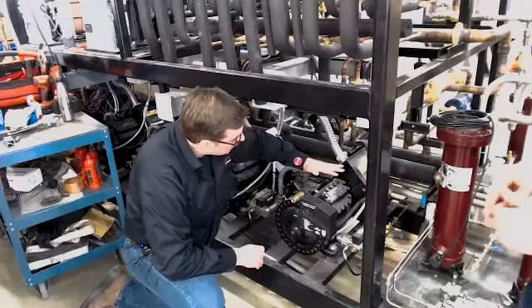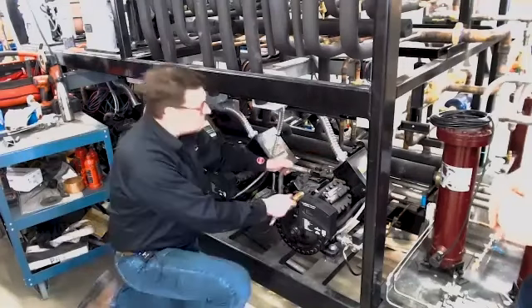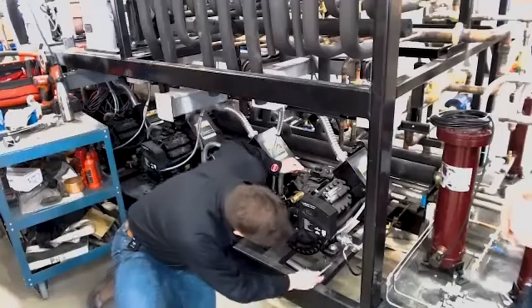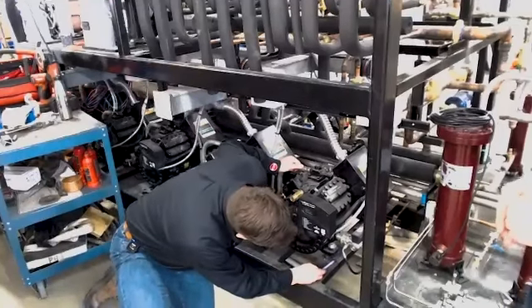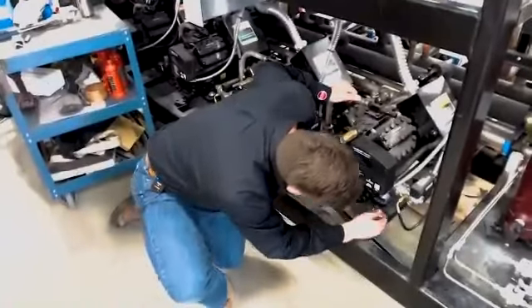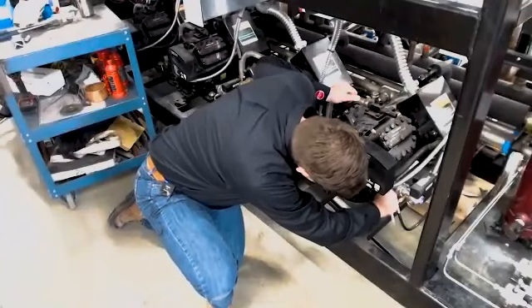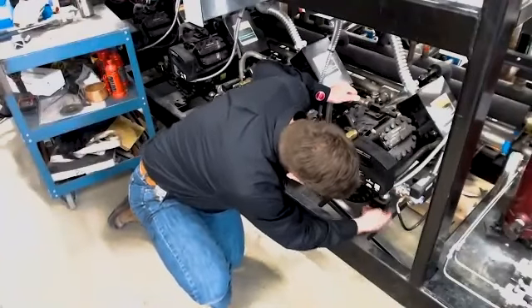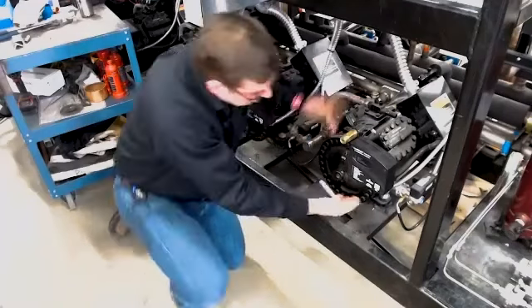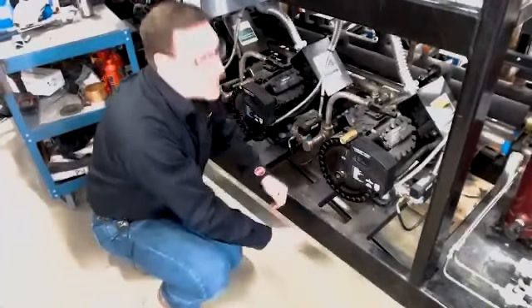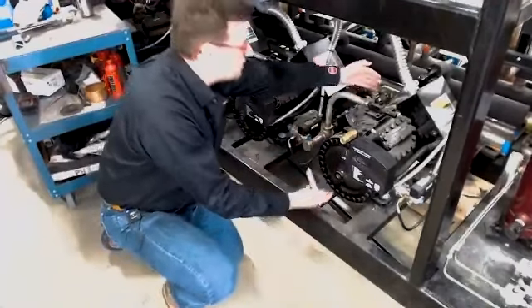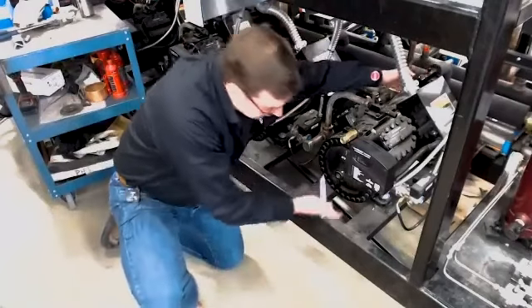We can take our discharge service valve off, and it's going to hold in place. We've got two blocks down here - a heavy steel block and then a heavy rubber grommet underneath. You want to take these bolts out - they're still loose right now because they're not set. We want to knock these out, you can tap them out. The compressor's going to fall about 2.5 inches. You knock out your bolts in the back, take off your service valve, and it slides right out.